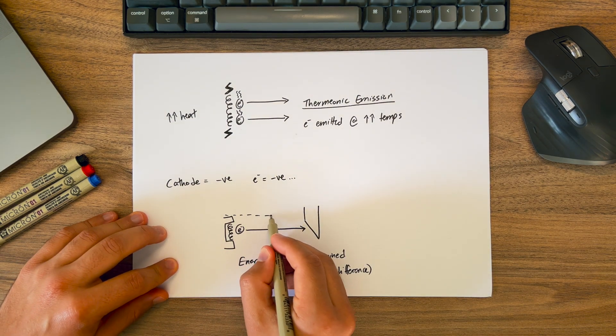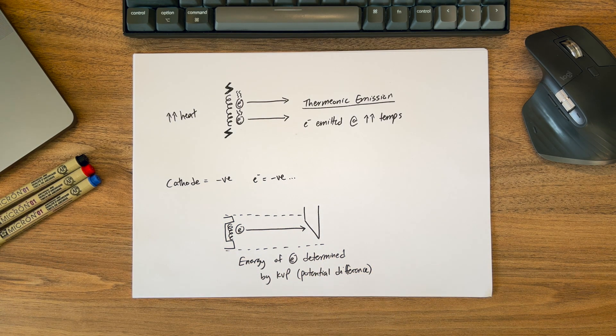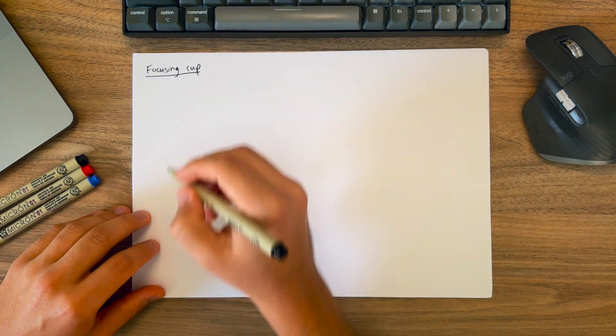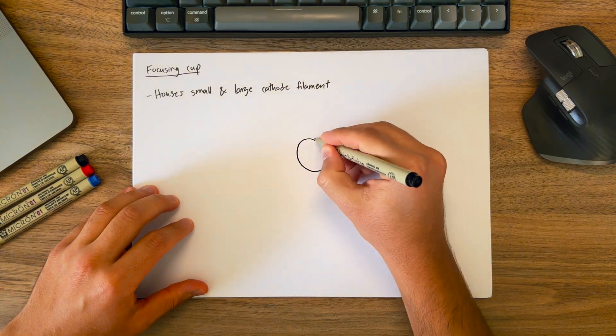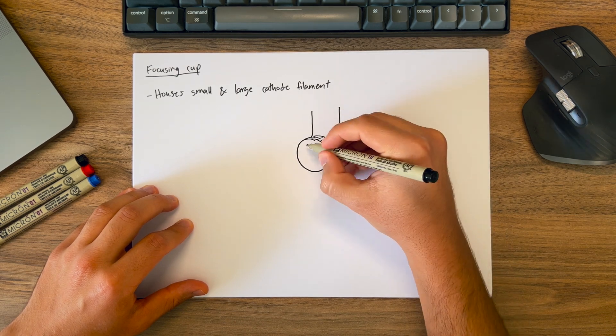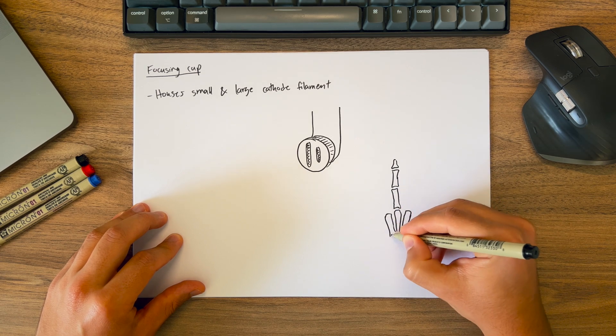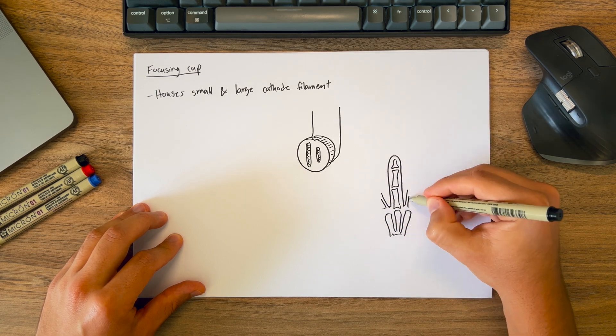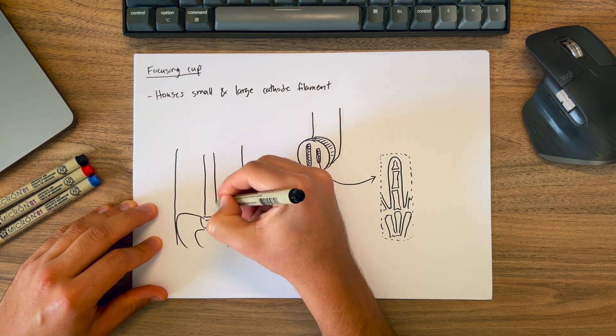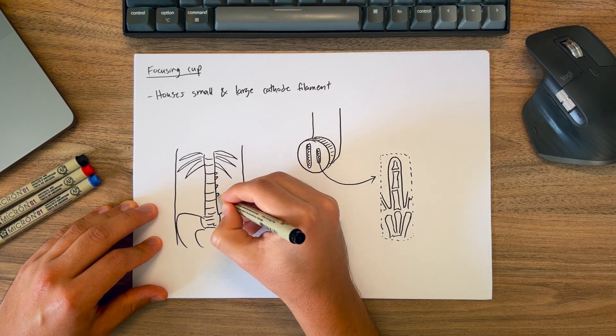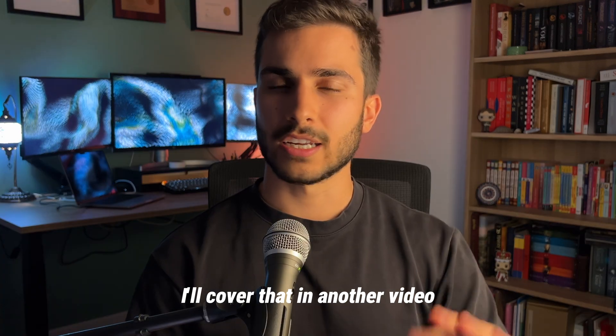The cathode is positioned within the x-ray tube so that the electrons emitted are precisely directed towards the target area on the anode. The small and large cathode filaments are housed within what's called a focusing cup, which focuses the beam of electrons directly towards the anode. So for example, if I'm trying to x-ray someone's finger and I need the highest resolution possible, then I choose the fine focus setting — the smaller filament will be activated. And if my next patient is coming in for an abdomen x-ray, I'd select the broad focus, and so the larger filament will be used.